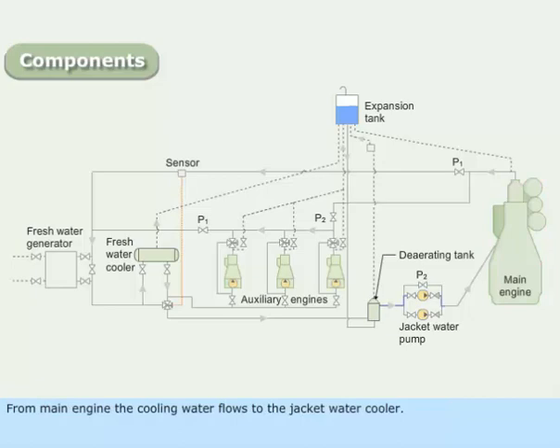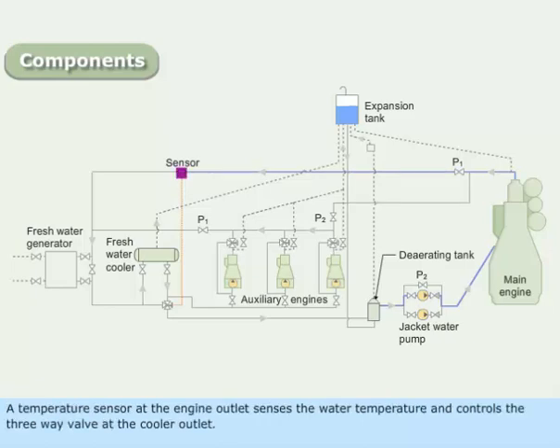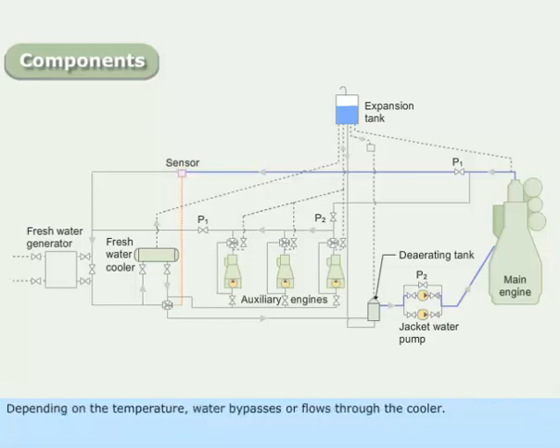From the main engine, the cooling water flows to the jacket water cooler. A temperature sensor at the engine outlet senses the water temperature and controls the three-way valve at the cooler outlet. Depending on the temperature, water bypasses or flows through the cooler.